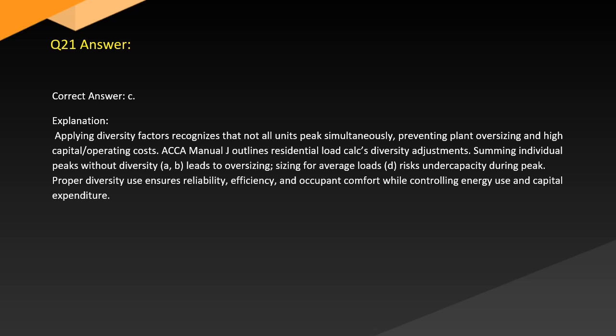Applying diversity factors recognizes that not all units peak simultaneously, preventing plant oversizing and high capital and operating costs. ACCA Manual J outlines residential load calculation diversity adjustments. Summing individual peaks without diversity, A and B, leads to oversizing. Sizing for average loads, D, risks undercapacity during peak. Proper diversity use ensures reliability and occupant comfort while controlling energy use and capital expenditure.